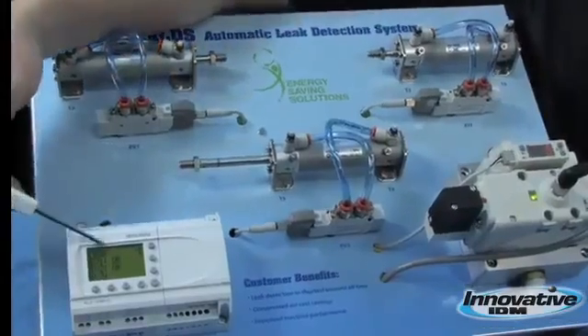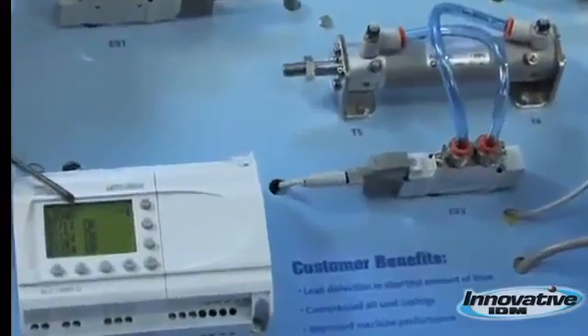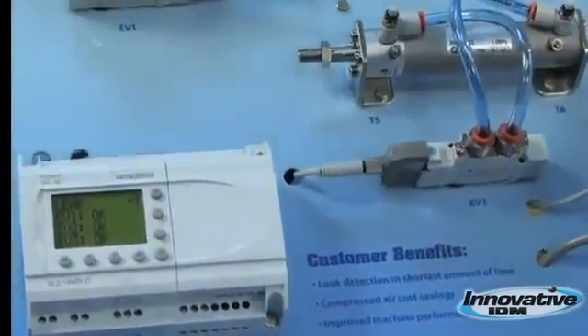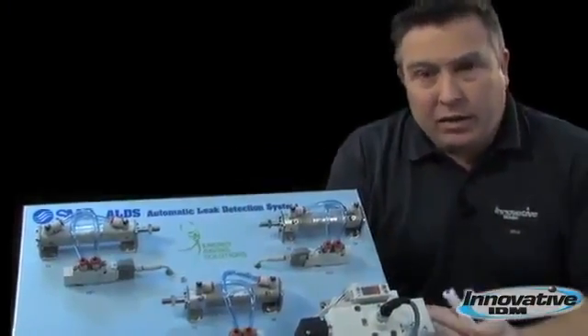And as we can see, they've all gone back based off of the baseline. So we fixed the leak. We just saved a lot of time and a lot of pain trying to find that leak.